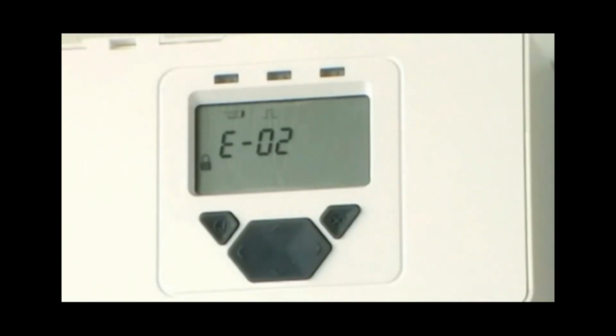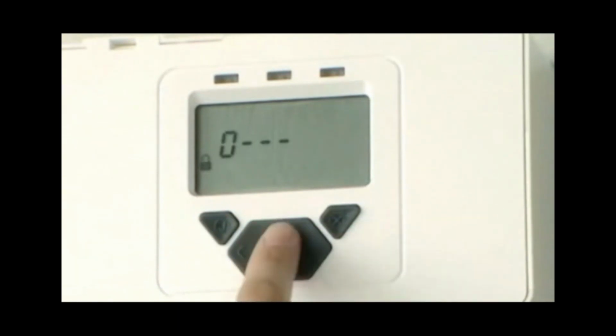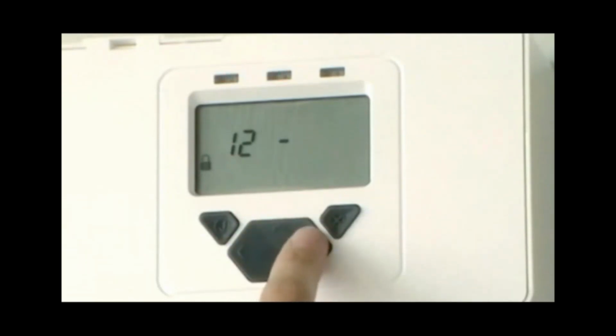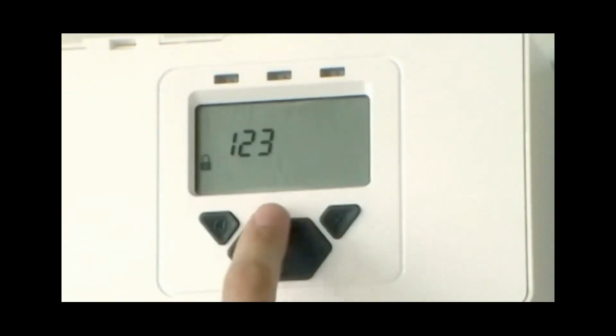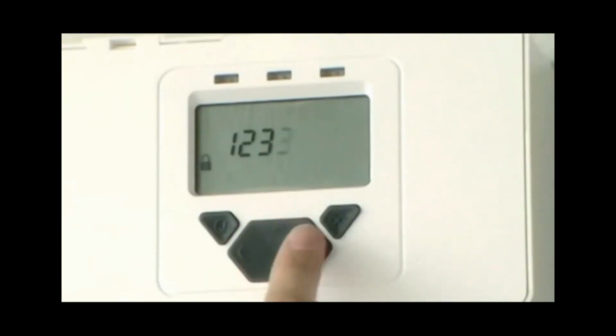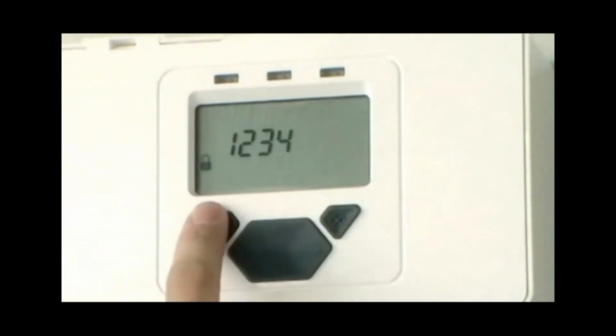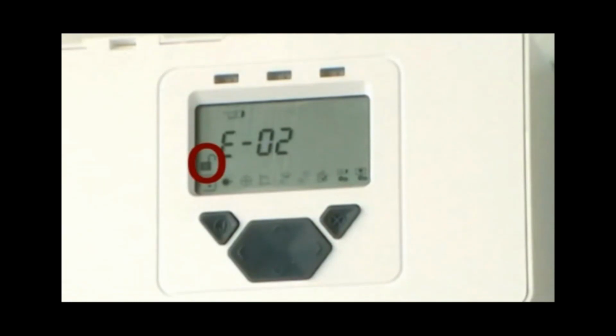To align the system, access the Engineering menu by entering the passcode using the keypad. The default is 1, 2, 3, 4. The padlock symbol will be unlocked, and you will now be in the Engineering menu. The next step is to find how many receivers are connected to the system controller.